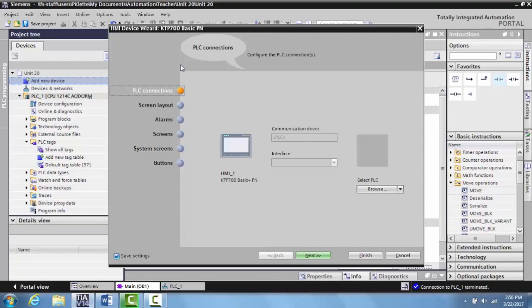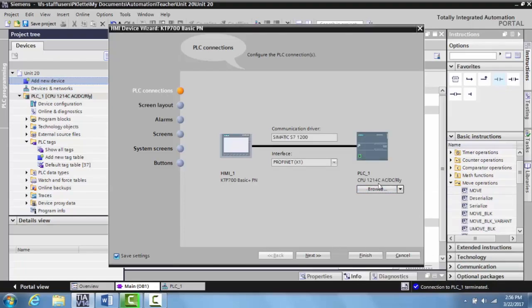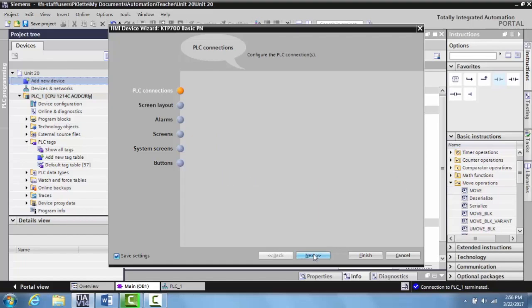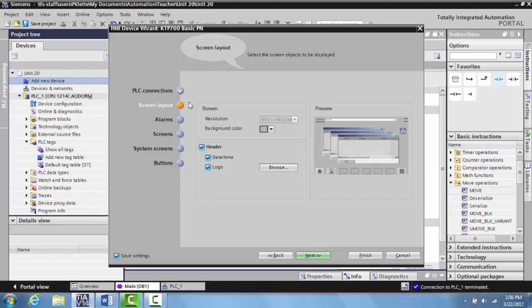Now we're in the HMI wizard. We want to select a PLC that it's going to be networked to, so we'll select PLC1, which is our S7-1200 and the TII Trainer. Select okay, and it's found that and shows these two are now networked together. Then we select next to go to the screen layout – we can select the date and time, get rid of the logo if we want. We'll get rid of the logo and leave the date and time in the header.